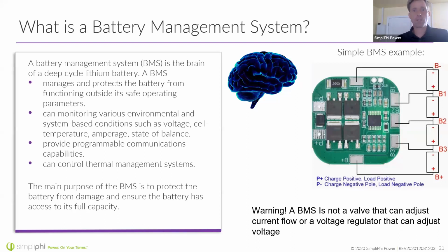So a BMS manages and protects the battery from functioning outside of its safe operating parameters. It can monitor various environmental and system-based conditions such as voltage, cell temperature, amperage, state of balance, state of charge, etc. It can provide programmable communications capabilities as well. So a BMS can offer the ability to change settings, to talk to external equipment, and it can also control thermal management systems in some cases. The main purpose of the BMS is to protect that battery, to keep it running in its designed operating parameters, right? So that we can access the full capacity and the full longevity of the life of that battery.